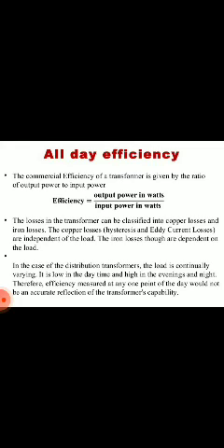In the case of distribution transformers, the load is continuously varying. It is low in the daytime and high in the evenings and night. Therefore, the efficiency measured at any one point of the day would not be an accurate reflection of the transformer's capability. Now we have the all day efficiency measurement of distribution transformers. The formula for the all day efficiency of the distribution transformer is as shown here.